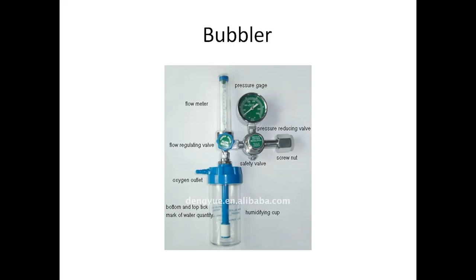not very exciting devices. The first one here is a bubbler. The bubbler does nothing more than allow oxygen to flow through a vessel of sterile water. As the dry gas or oxygen from the wall or the tank flows up through the water, sterile water, it takes on a small amount of humidity and provides some comfort to our patient. The humidity amount is low, and we typically just use this in nasal cannula type patients, and it's really effective for flows of 3 to 6 liters. Any flow below that, there's usually not enough gas flowing through there to really make a difference to the mucosa.